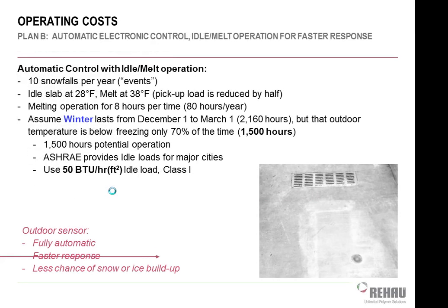All right, so the Plan B example is to put an automatic system in. This particular automatic system is one of the ones they're showing in the picture here, where you put the sensor in the actual concrete. We typically call that the hockey puck sensor because it looks like a hockey puck, obviously. So you've got the concrete going around that, and this device will detect if I need to run the snowmelt system based on snow accumulation, temperature, and moisture.